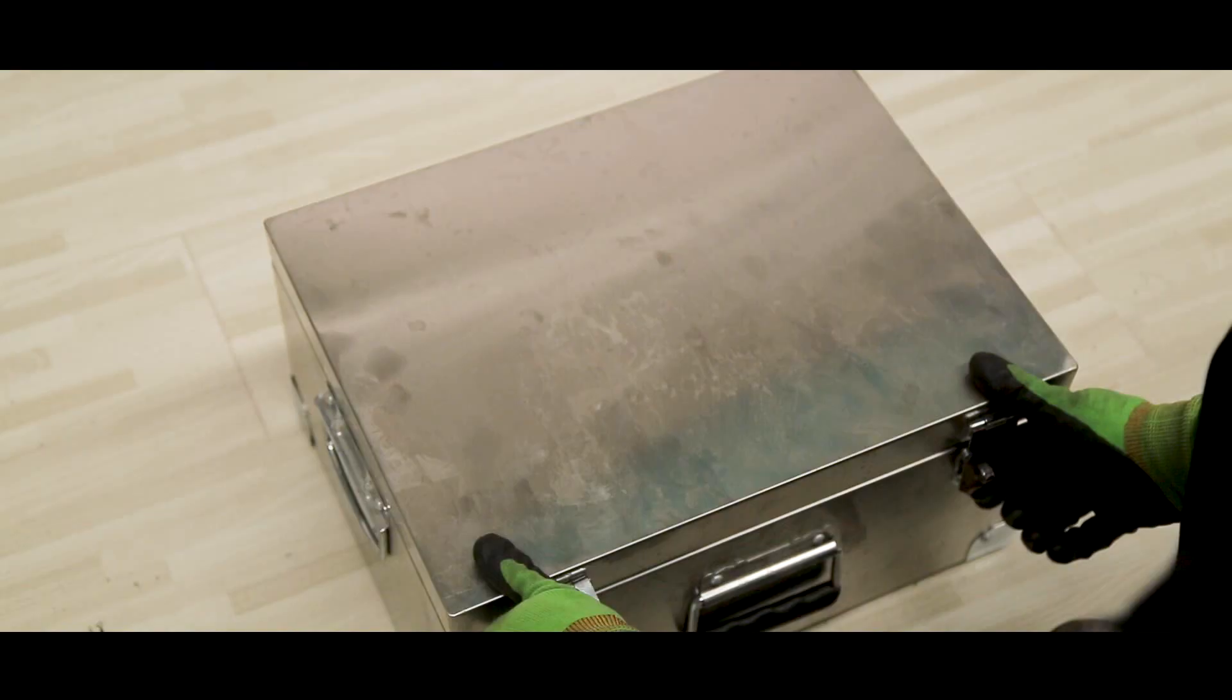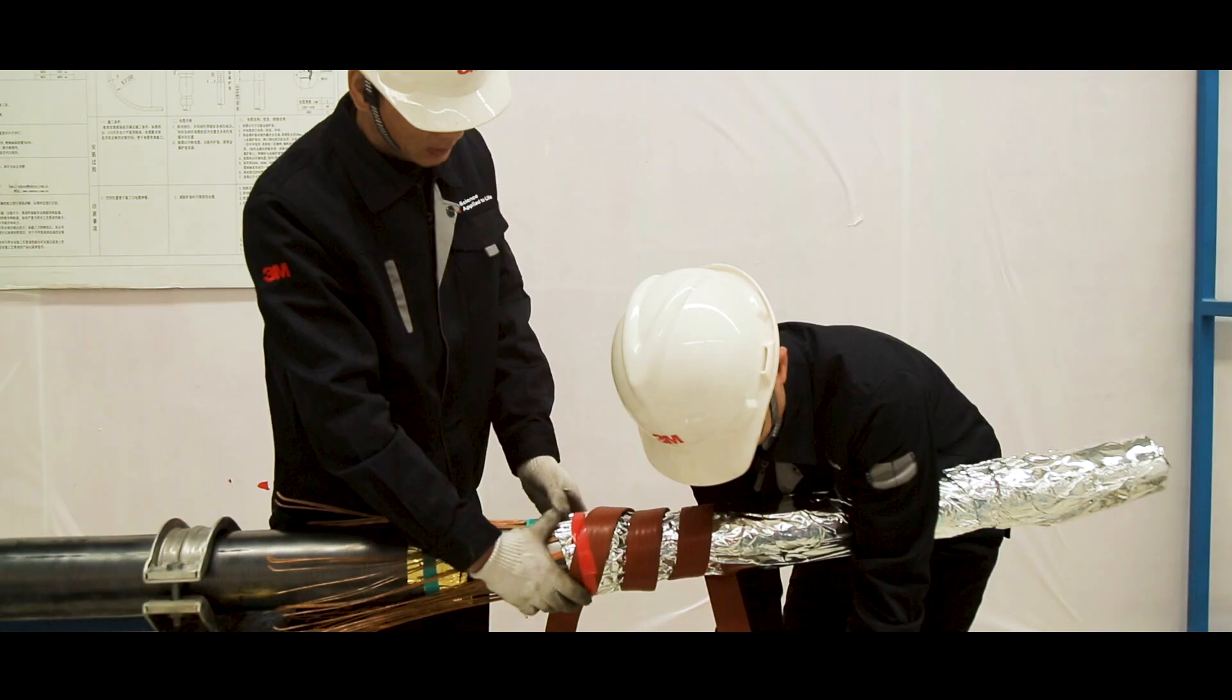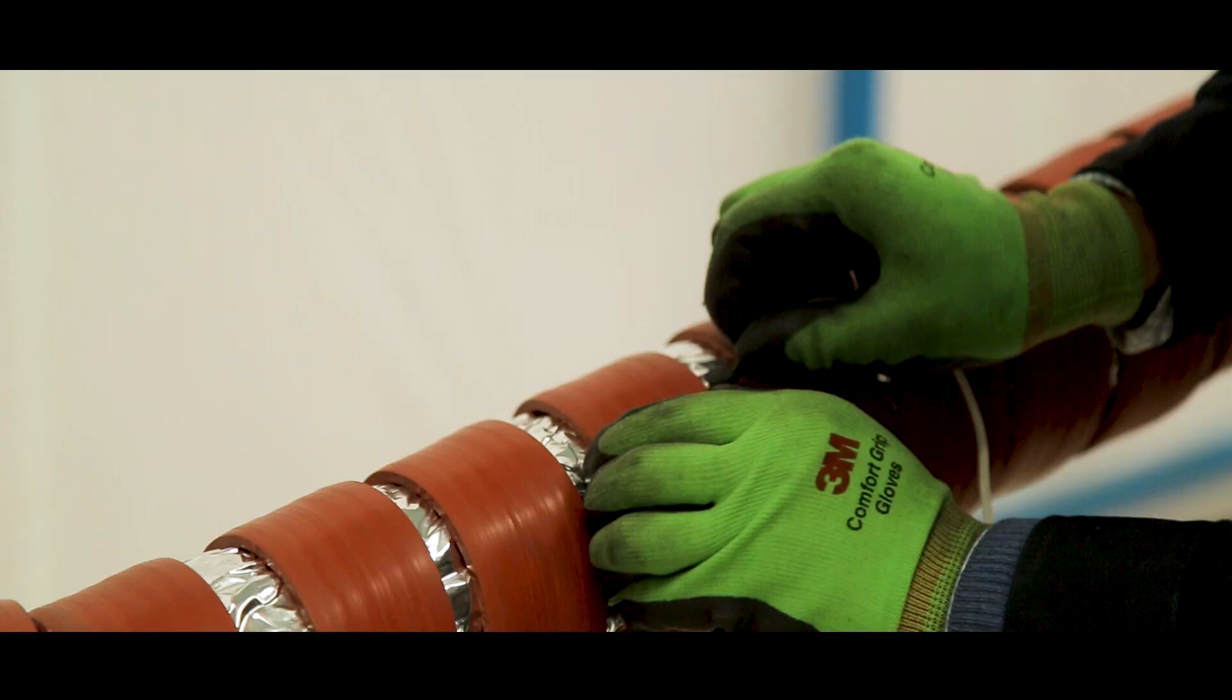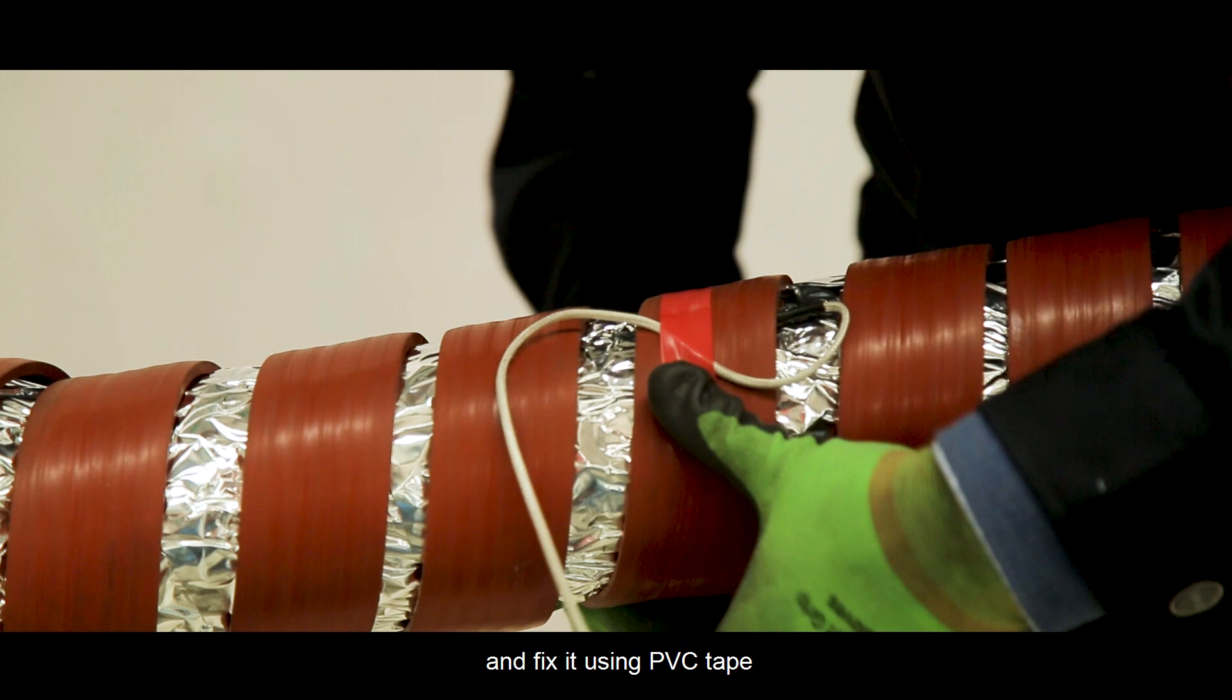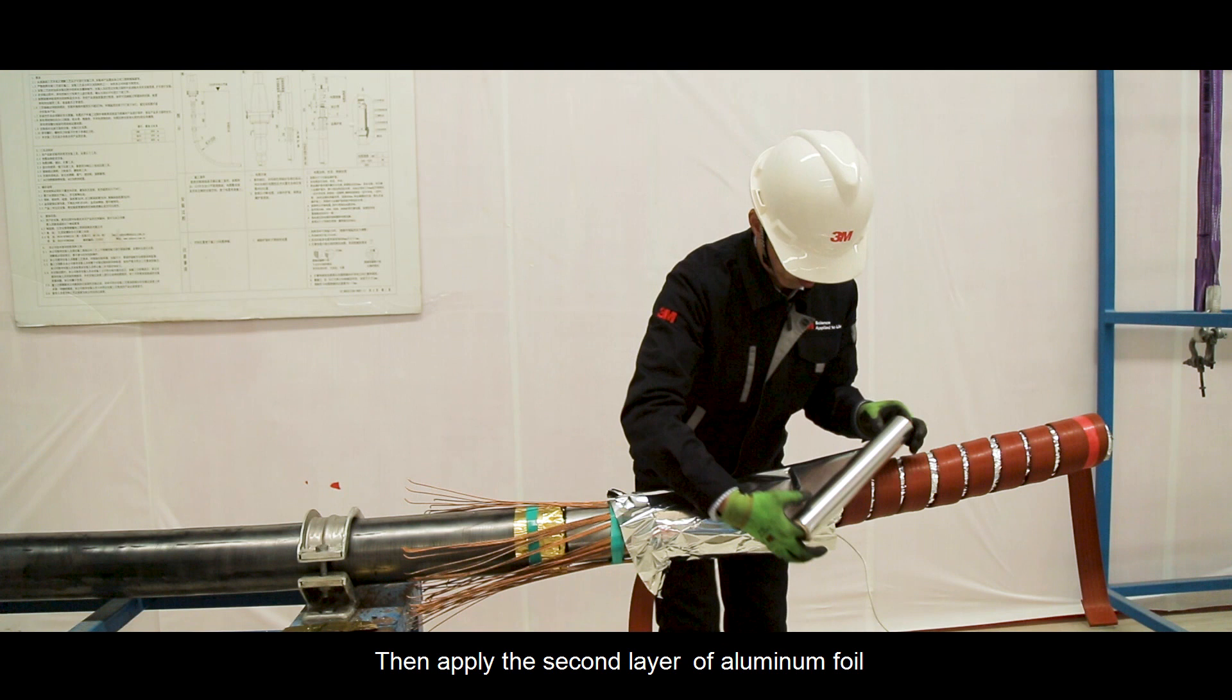Apply aluminum foil on the cable. Overwrap with evenly distributed heating tape. Insert temperature sensor under the heating tape and fix it using PVC tape.